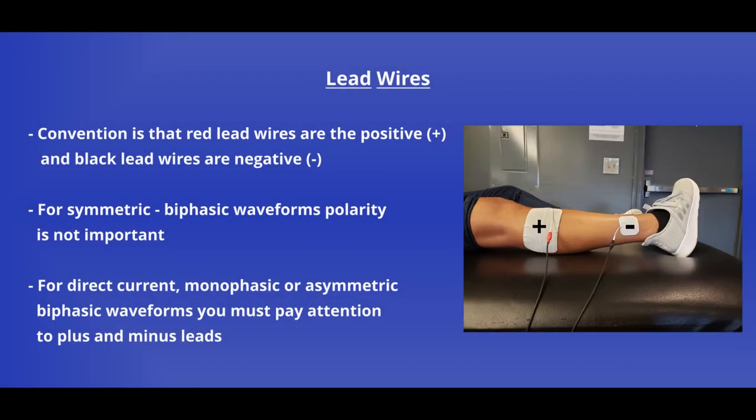Finally, we have our lead wires, which carry our current from the control unit to the electrodes. To complete the electrical stimulation circuit, we're going to need two electrodes and two wires. Leads are usually color-coded. The standard is to use red for positive and black for negative. However, that might not be the case always. For symmetric biphasic currents, it doesn't matter which one is plus and which one is minus. But when using direct current or unbalanced AC current, knowing where to put the positive and the negative electrodes is extremely important.